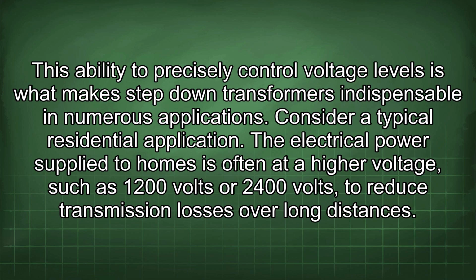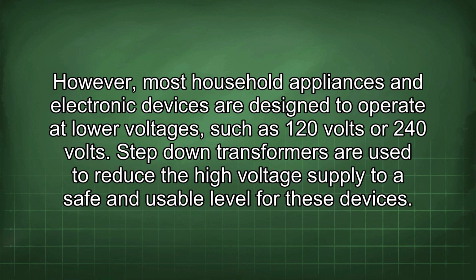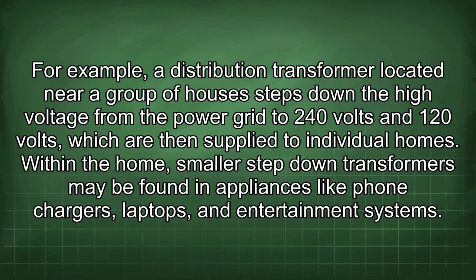Consider a typical residential application. The electrical power supplied to homes is often at a higher voltage, such as 1200 volts or 2400 volts, to reduce transmission losses over long distances. However, most household appliances and electronic devices are designed to operate at lower voltages, such as 120 volts or 240 volts. Step-down transformers are used to reduce the high voltage supply to a safe and usable level for these devices. For example, a distribution transformer located near a group of houses steps down the high voltage from the power grid to 240 volts and 120 volts, which are then supplied to individual homes.